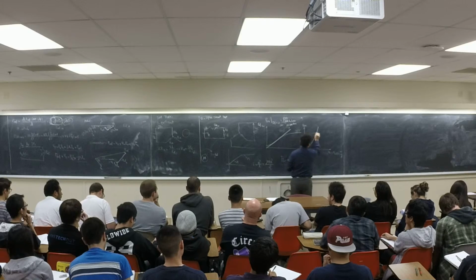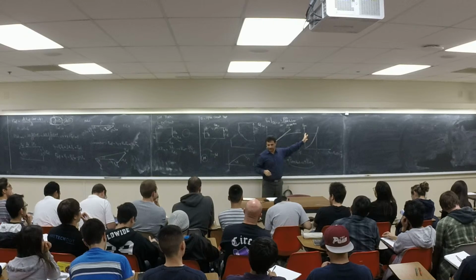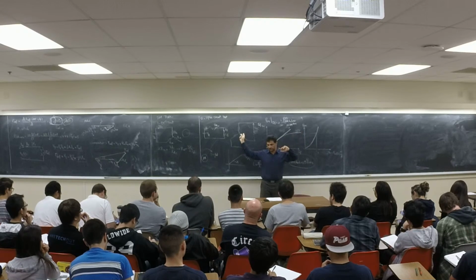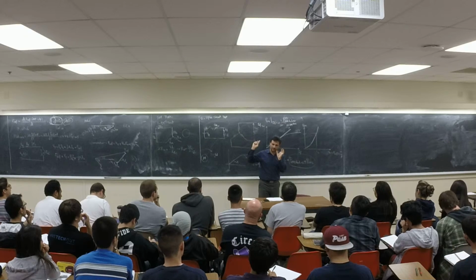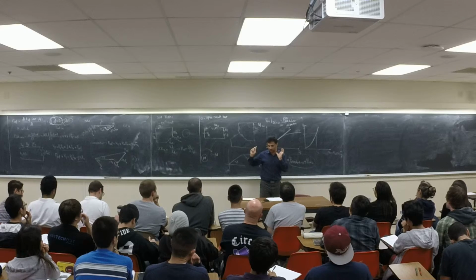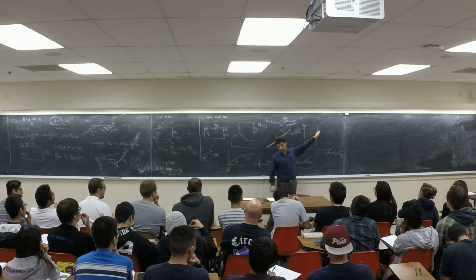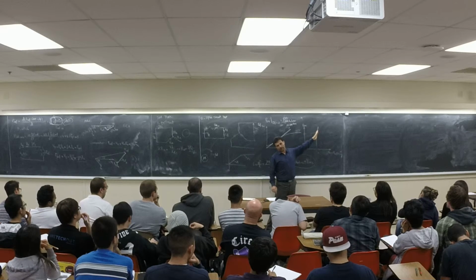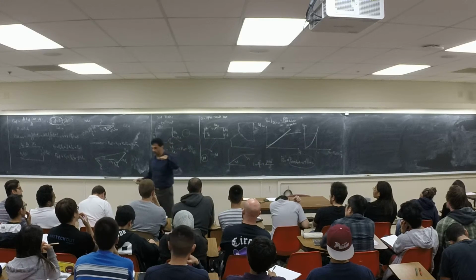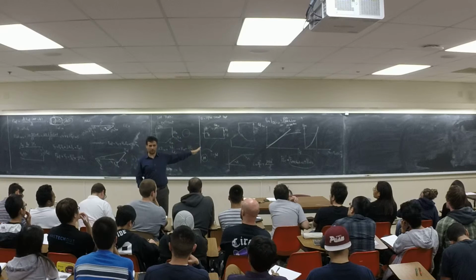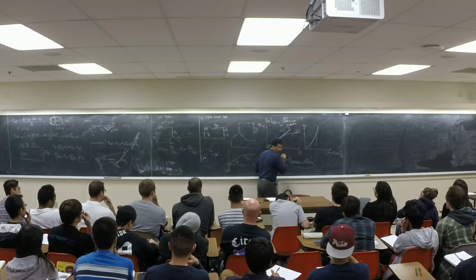For example, this is the rated voltage, Vn. So you have some values here, right? Basically, if the speed is fixed, this is going to be fixed. This is synchronous speed. This is not like an induction machine where the speed is going to change, or where it changes a little bit based on the slip. Frequency is fixed, and if you are at the rated voltage, core loss also is going to be fixed, right? With different loads, core loss still is going to be fixed. You are at the rated voltage and the rated frequency, so the core loss will be fixed and mechanical loss will be fixed. They call this one constant power loss.